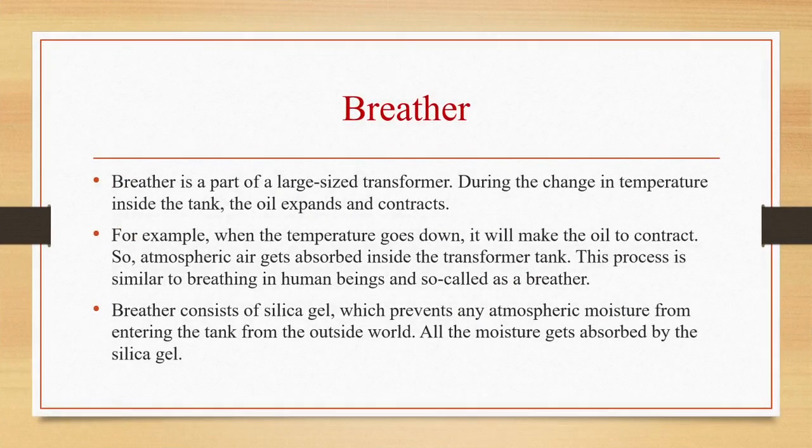Breather. Breather is a part of large size transformer. During the change in temperature inside the tank, oil will expand and contract. For example, when the temperature goes down, it will make the oil contract. So atmospheric air will get absorbed inside the transformer tank, and this process is similar to breathing in human beings, and so it is called a breather.